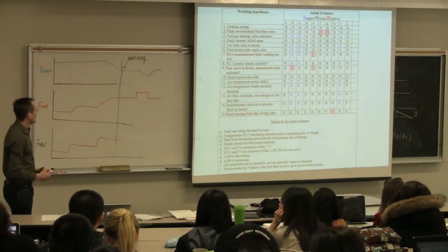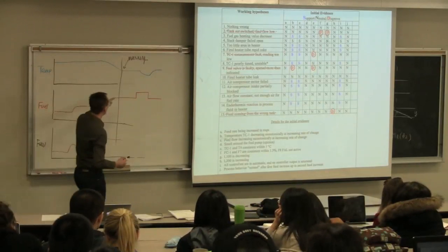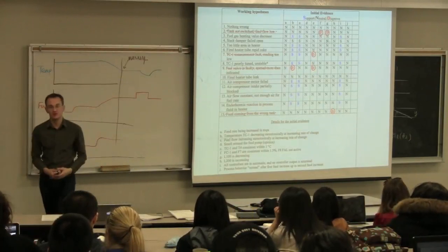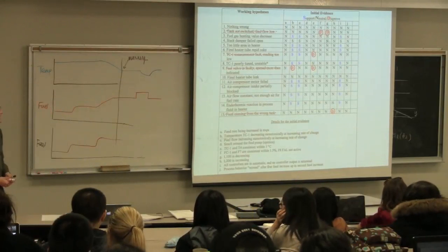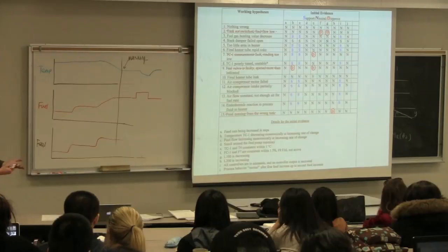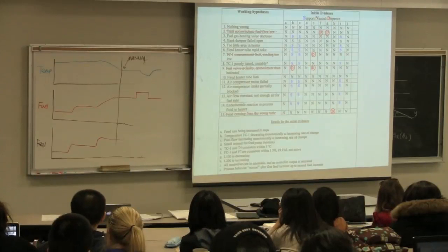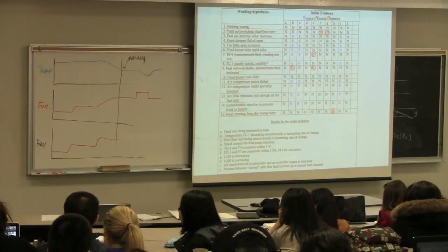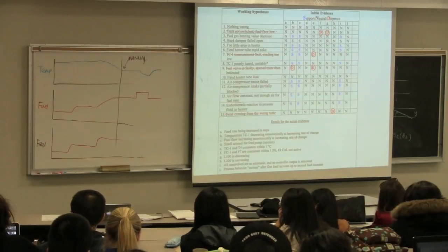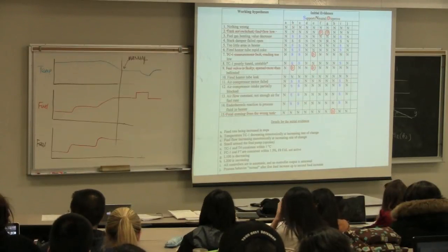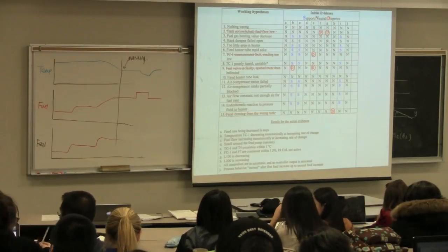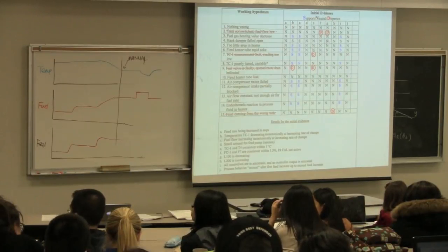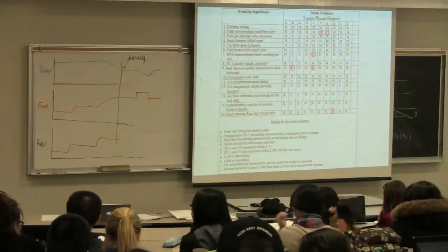So at the end of this, the fact that we can place the control loop in manual and do this test helps us solve that issue. It is a diagnostic test that may not be obvious to consider, but it helps solve this particular case study. When it comes to troubleshooting, it's not always clear what should be done. But I think what will help you a lot is if you look at this table.